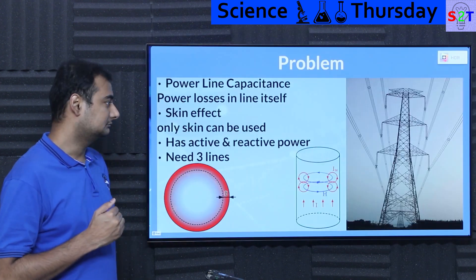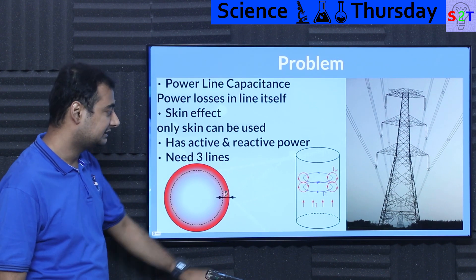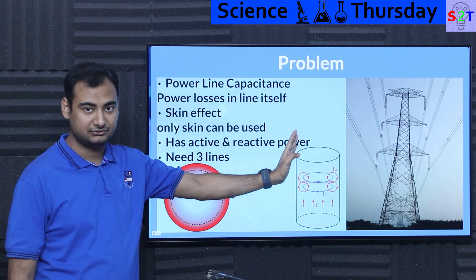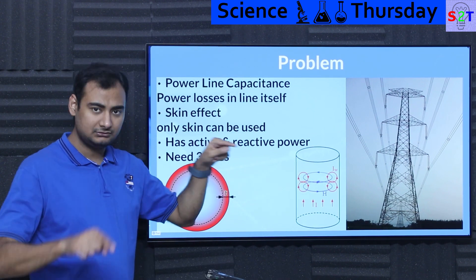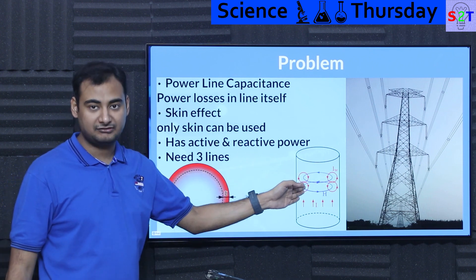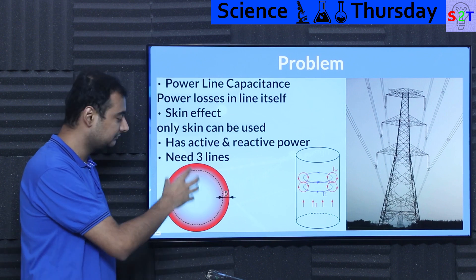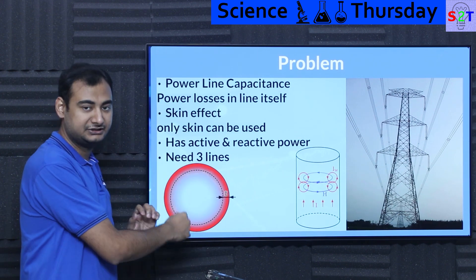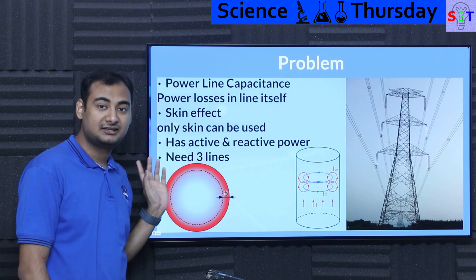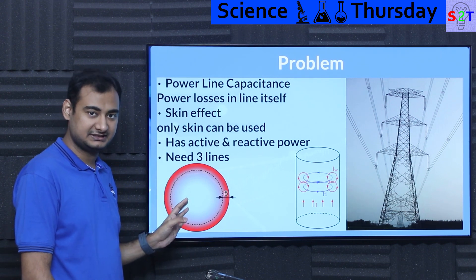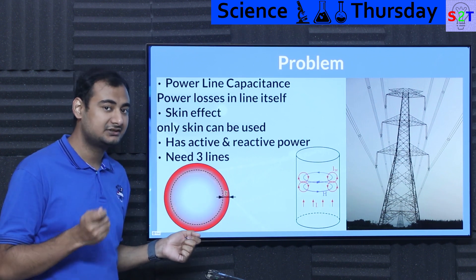On top of that you also have to deal with what we call skin effect. If you have a conductor with a lot of energy going through it, it creates a magnetic field — no problem. However, it also creates eddy currents: small currents that create another magnetic field that fights the first one. The consequence is the center always remains empty and the outer skin carries most of the charge. So a cable rated to carry 50 amps would barely carry 25 amps because the center is unutilized. Higher the frequency, the worse this effect — so a cable in India carries more than in the USA simply because the USA is at 60 Hz and India is at 50 Hz.